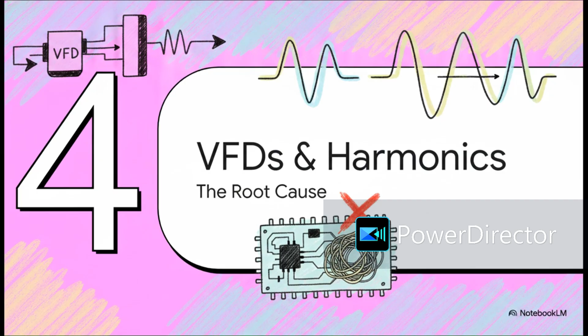You have to confidently explain the internal mechanics of a VFD and exactly how power is transformed inside that drive. So you walk them through the 3 exact steps of power conversion. First, you explain that the facility operates on a standard 3-phase AC supply. But a VFD needs a stable baseline to rebuild the frequency. So step 1, the VFD uses a rectifier bridge to convert that incoming AC into direct current, or DC, which gets smoothed out over a DC bus.